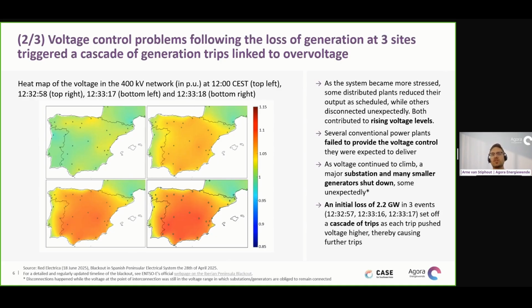And so what then starts to happen is that a cascade of trips caused by voltage issues is set off, because as each power plant disconnected because of the way voltage control was managed in Spain, it actually led to a further increase in voltage, which then caused other plants to experience over voltage, or a voltage to that level that they in turn disconnected, and a cascade like this was set off.